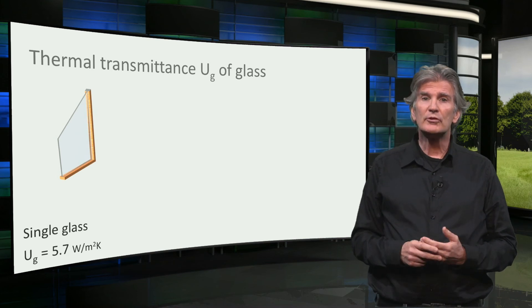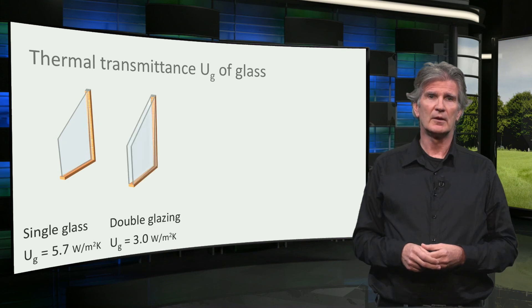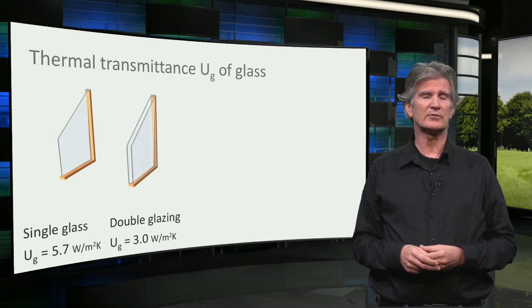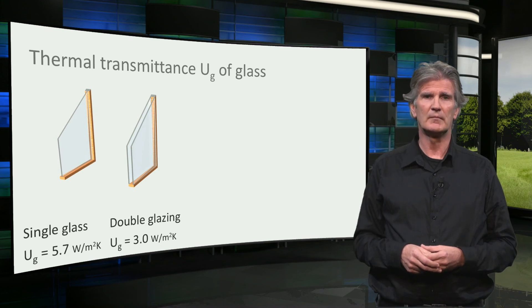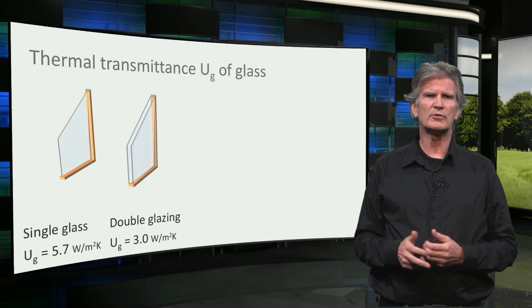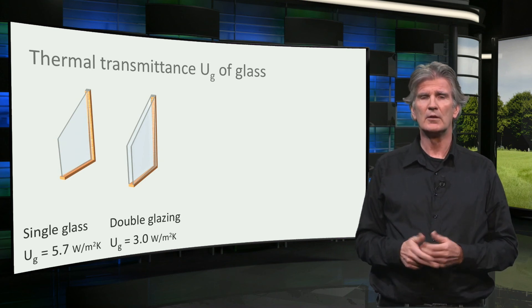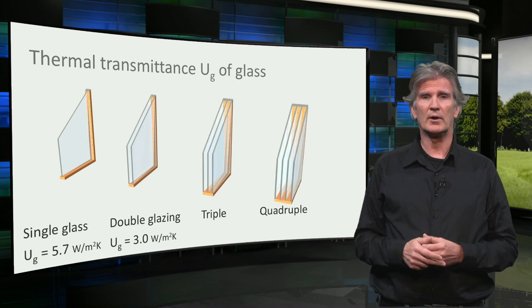To reduce the U-value of glass, a few technologies are applied. First, adding additional layers of glass, thus creating one or more air cavities. By adding one extra layer, double glazing is created with a U-value of 3, which almost halves the heat losses compared to single glass. Double glazing is common nowadays. Triple glazing is more and more applied, and even quadruple glazing is on its way.